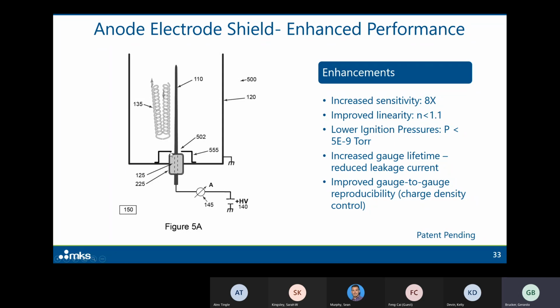We also increased the gauge lifetime because this shield provides mechanical protection for the feed-through. Any material that gets sputtered off the walls that could coat the feed-through and provide leakage current, which affects accuracy, is now shielded by the anode shield. So we found enhanced lifetime simply because of the addition of the anode shield. And because the boundary conditions are now very well defined, there is no charging in the feed-through to deal with anymore. We also have improved gauge-to-gauge reproducibility, so a much more consistent product.